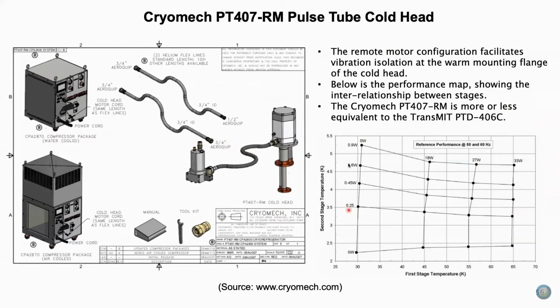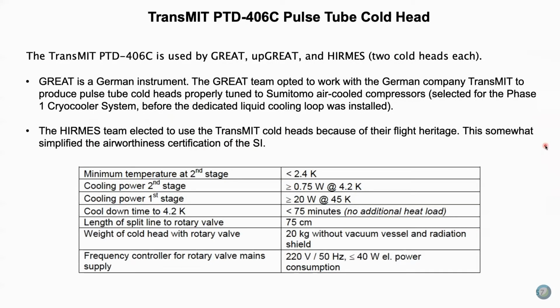Here's a performance map. This is kind of difficult to get used to, but I'm just showing it to give an idea of the cooling capacities. These roughly vertical lines are lines of constant cooling capacity on the first stage, the warmer stage. The roughly horizontal lines are lines of constant cooling capacity on the colder second stage. And then we have the temperatures on the first and second stages. So it's possible to read off, based on how much heat you're putting on the two stages, what the temperatures should be, and vice versa, as long as that performance map is well calibrated, that is.